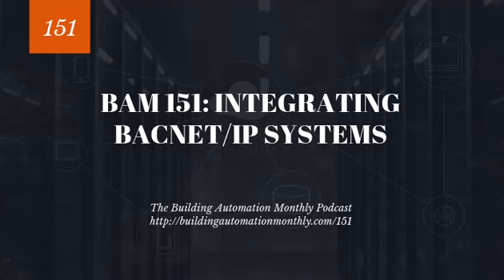Okay, so now we've started to draft out our system architecture. Now, how's the data going to flow? This is really, really important because this is where stuff starts to get messed up. This is where folks start to not understand that BACnet IP analog and binary values have priority arrays, and we're not writing to the right priority array, and maybe we're writing to a higher level on the priority array, meaning that it has less impact. So the higher on the priority array, the less impact. The lower on the priority array, the more impact, the more priority.